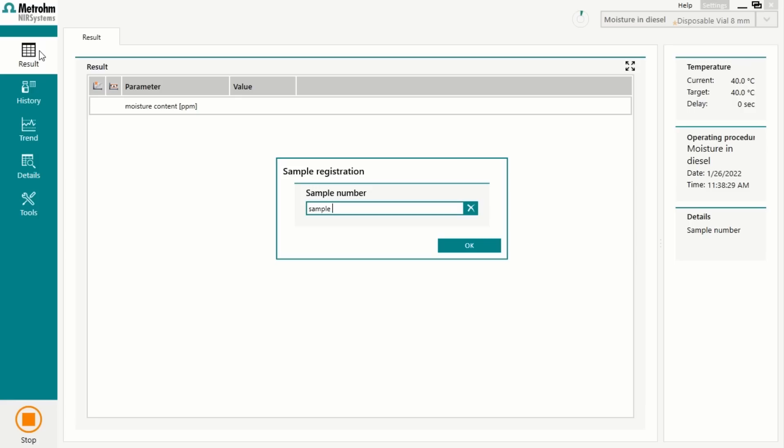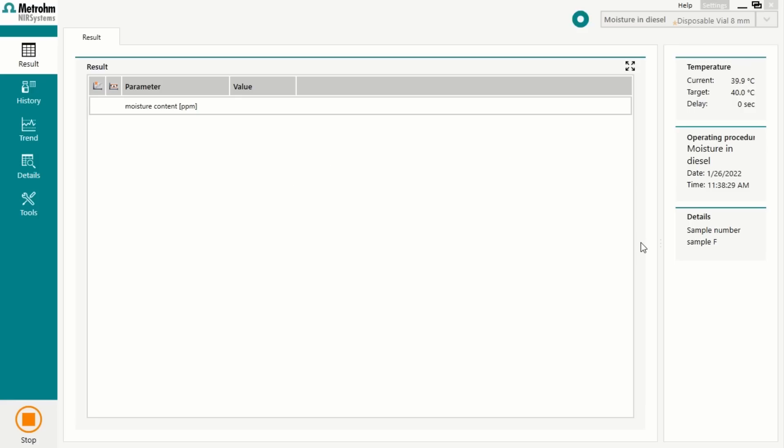To create such a prediction model, we need the absorption spectra of our sample on the one hand, and a reference value on the other. For our moisture example, we can use Karl Fischer titration to get the reference values. Whenever an unknown sample is measured, the model predicts the content of interest — in our example, moisture.